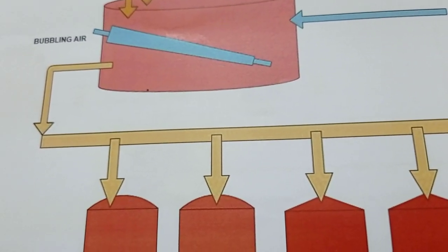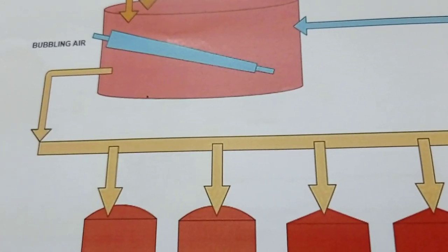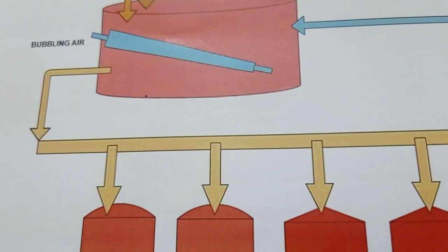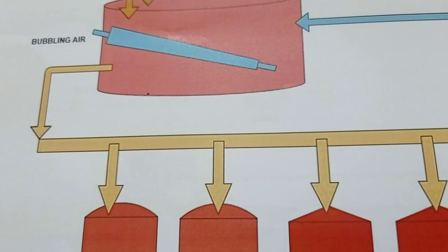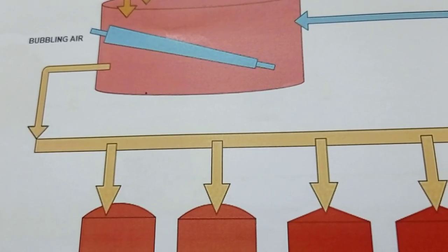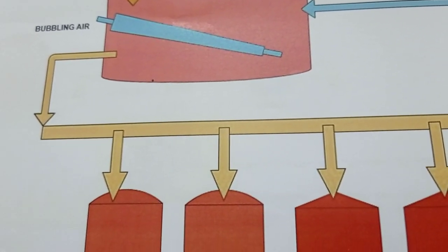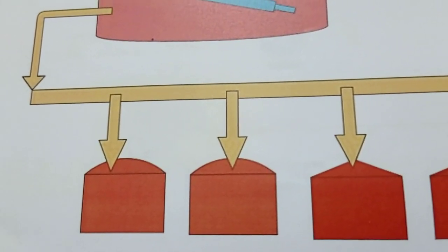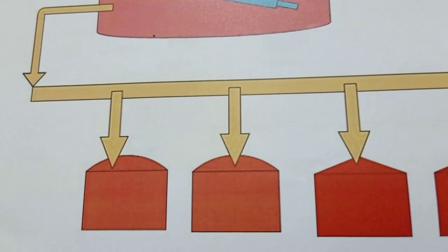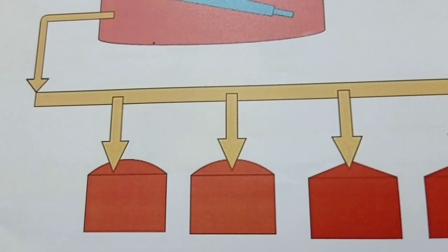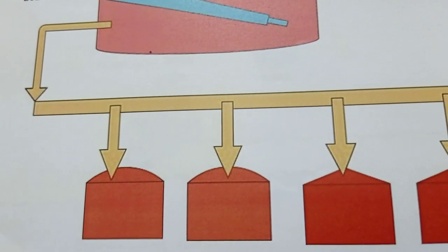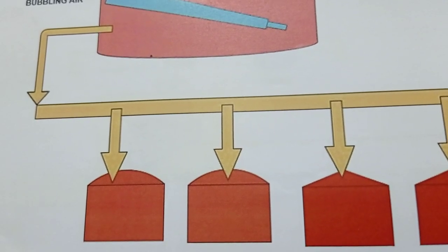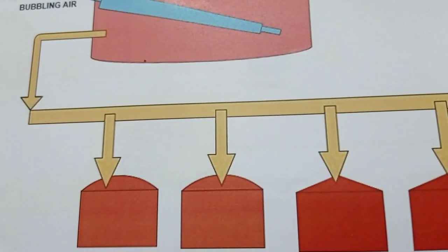And one more thing I want to say is how we handle a case of fire. The auto ignition temperature is 440. Even if there is no fuel and no source of ignition, it can generate fire at the auto ignition temperature of 440. So it does not need any type of fuel to burn. If there is a fire, how do we extinguish it in pits? For example, you have underground pits. If you find there is a fire, just close the pit so there is no ingress of oxygen and the fire may get extinguished. And another best method is to use steam.